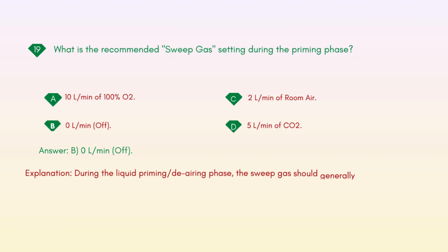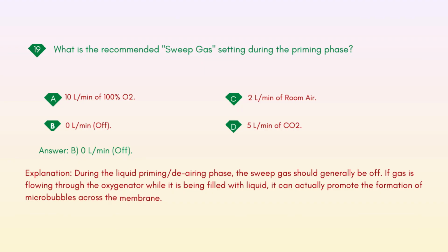Explanation: during the liquid priming/de-airing phase, the sweep gas should generally be off. If gas is flowing through the oxygenator while it is being filled with liquid, it can actually promote the formation of microbubbles across the membrane.